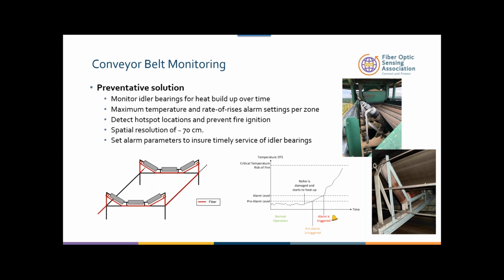Either you can activate a suppression system. It's very rare for conveyor belt, but at least you can stop your conveyor belt. So if the alarm is triggered, you can stop the conveyor belt and then go and check. This is before a fire happened. Fiber optic linear detection is now used in this case not just for detecting a fire, but it can also be used for preventative maintenance. That is not the case for conventional linear detection.